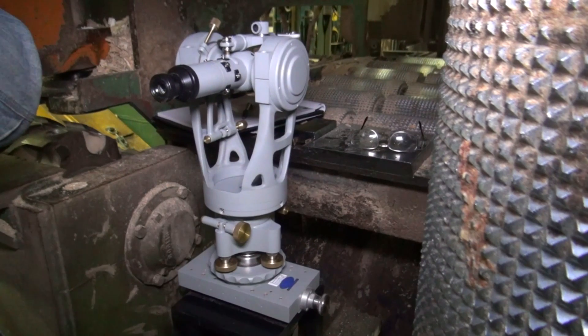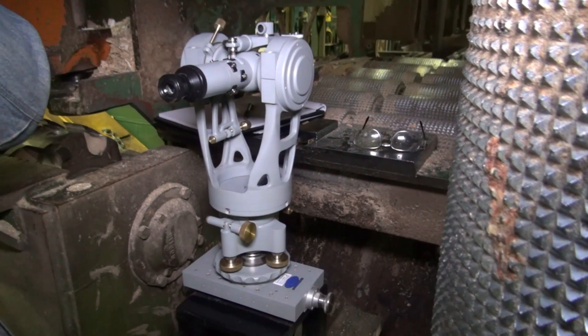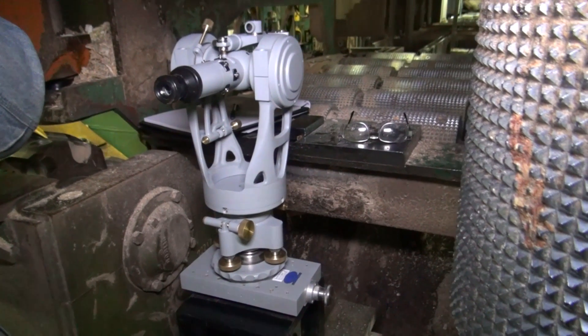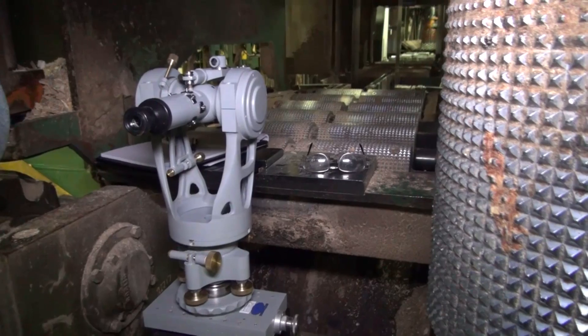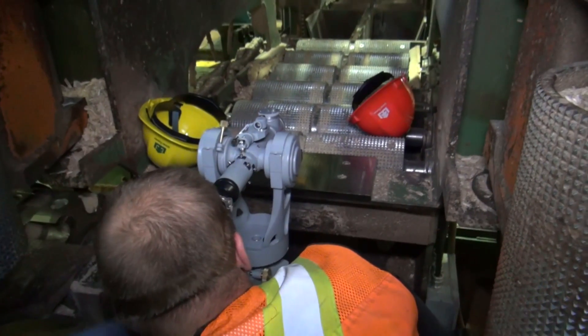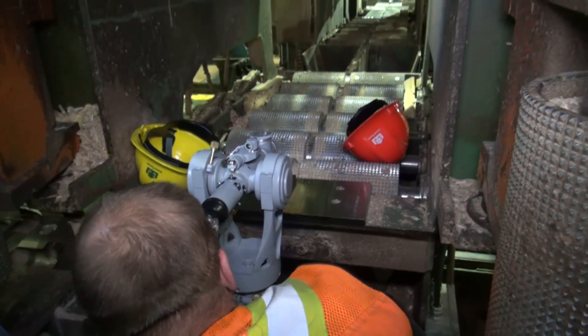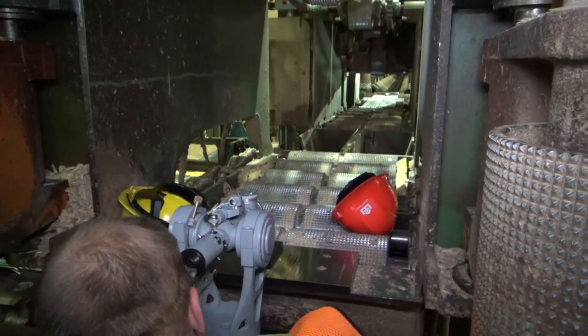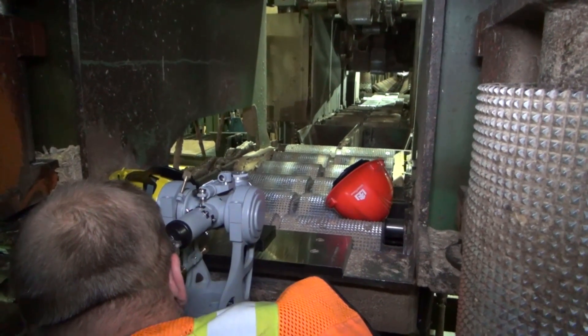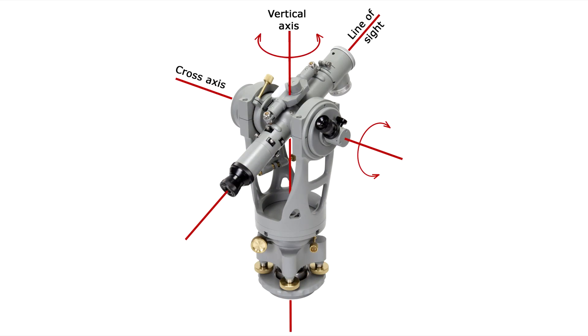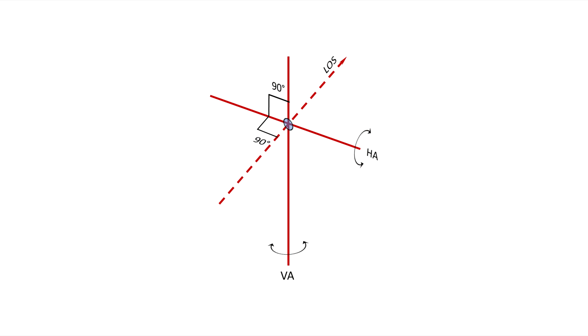The Brunson instrument we will use in this alignment process is called the jig transit. Specific geometric relationships exist between its mechanical and optical axes that allow it to sweep very precise horizontal and vertical planes. The axes are mutually perpendicular and intersect at a common point.